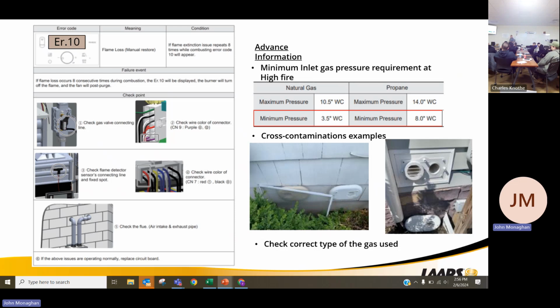Some of the things we want to pay attention to, especially if we're doing it residentially, is the gas meter large enough to handle the load. Most of our gas meters on a residential application are 225,000 BTUs. I now put in a 200,000 BTU gas appliance. All of a sudden, my gas meter's undersized. I have to fight with National Grid, PSE&G, whoever your gas provider is, to come get me a new gas meter.